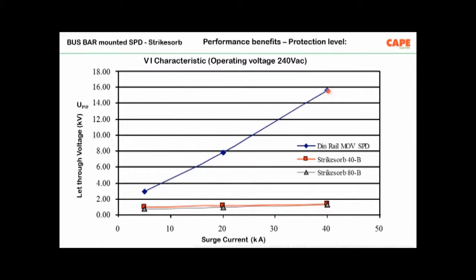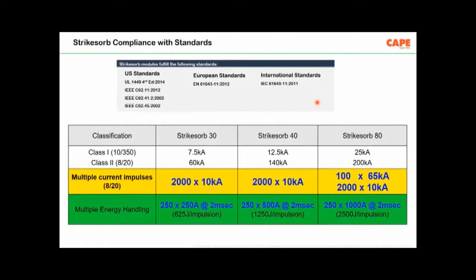Here, let us say, for example, a surge of 40 kiloampere, which is a very high surge, comes. The actual protection level offered by your DIN rail SPD is approximately 16 kV. In comparison, for the bus bar mounted SPD, the protection level is actually less than 2 kV, or something about 1 kV. So the problem with DIN rail mounted SPDs is that when the rate of change of current is higher and higher, there is more voltage drop on the connecting wire. As a result, most probably these devices won't protect your electronics. So you need to have a really good quality product or a good system like the bus bar mounted SPDs.